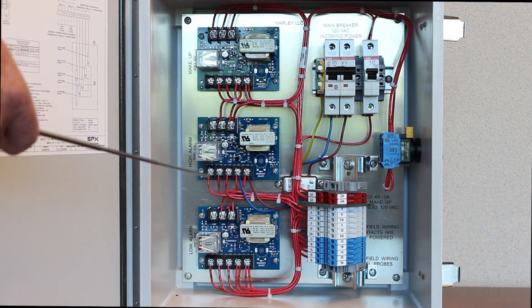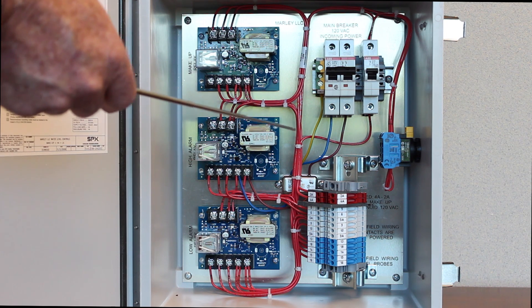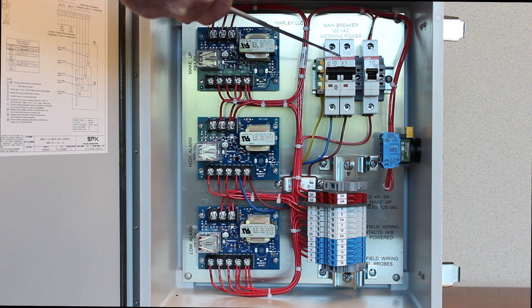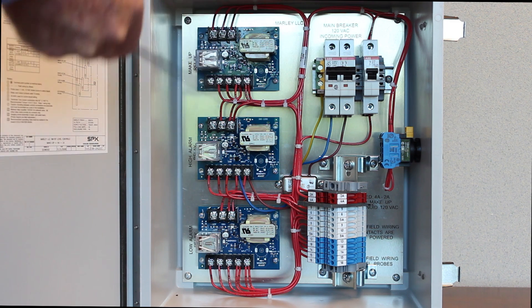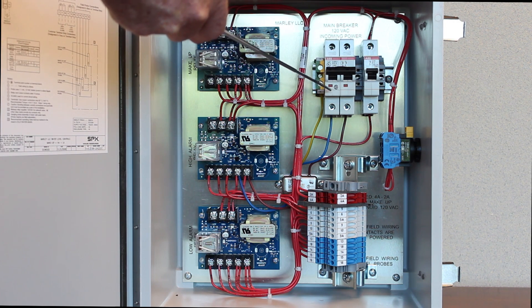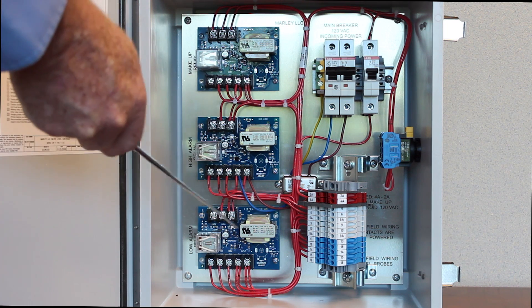Inside the enclosure I want to point out the internal components. We have a main circuit breaker that receives the 120 volt AC power supply from the customer, or in some cases it might be a 220 volt supply. This main circuit breaker has thermal magnetic short circuit protection providing protection for the control panel. Once the power flows through the circuit breaker it flows to the individual cards here.